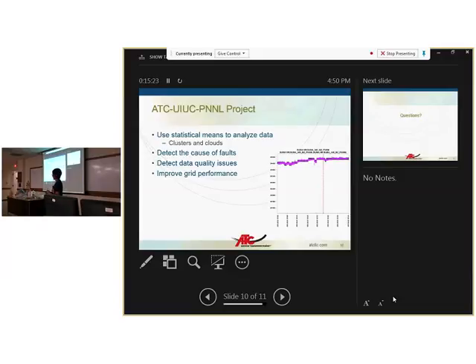One thing we want to try to do is detect the cause of faults. If we know the cause, such as lightning, we can figure out what's happening during lightning. We can also detect data quality issues—if it's showing a zero out of nowhere, most likely the PMU isn't working at that time.